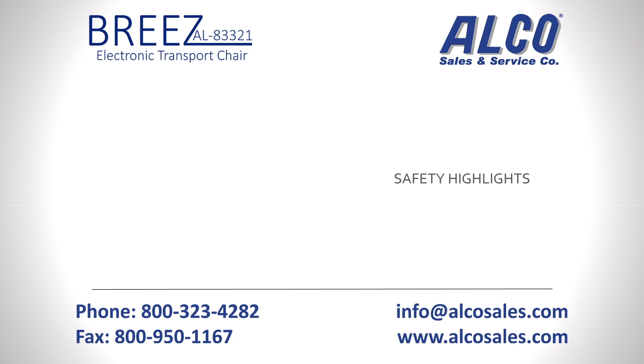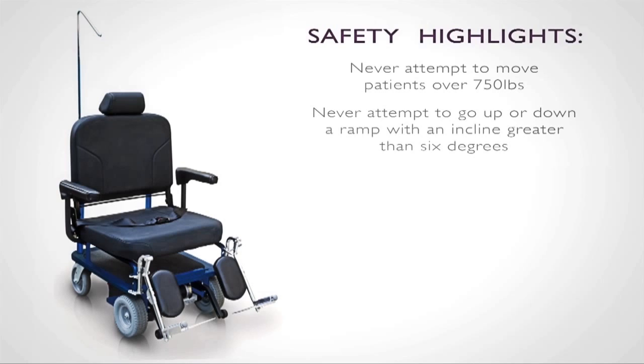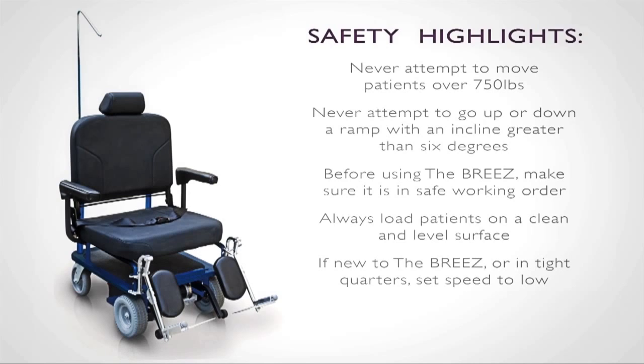Only trained staff should operate the Breez. Before operating, make sure that you have read and understood the topics covered in the owner's manual. Never attempt to move a patient that weighs more than 750 pounds with the Breeze, and never attempt to go up or down a ramp with an incline greater than 6 degrees. Before using the Breeze, make sure that it is in safe working order. Contact your maintenance department if you feel it might be malfunctioning. Always load patients on a clean and level surface with the rear casters locked. If you are in tight quarters or until you are comfortable driving the Breeze, set the speed control to low or the turtle.